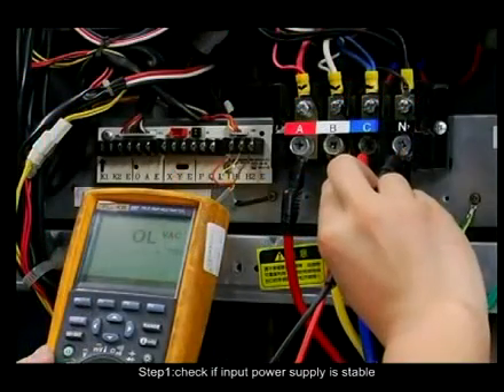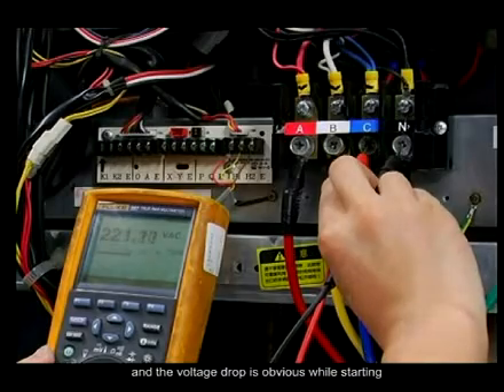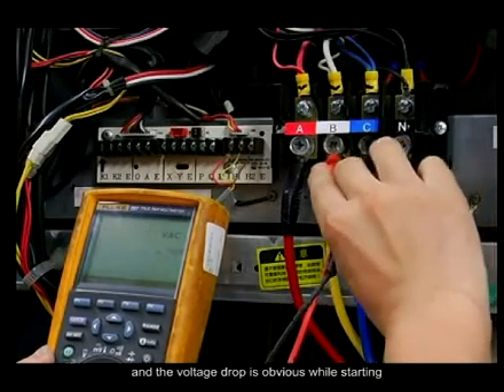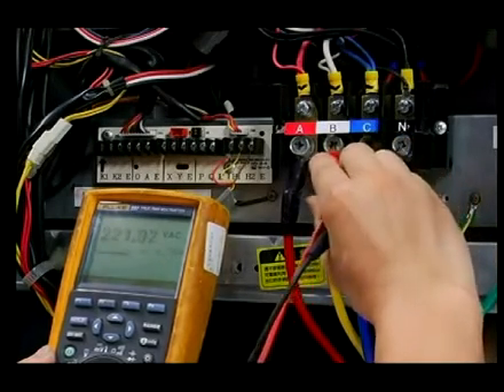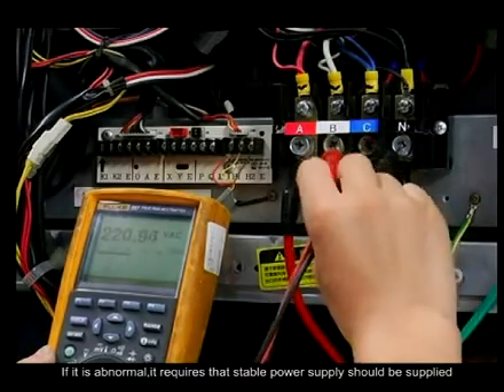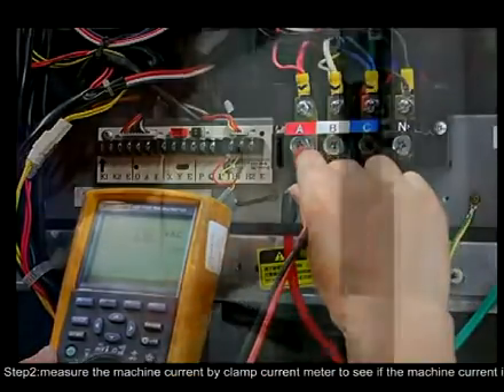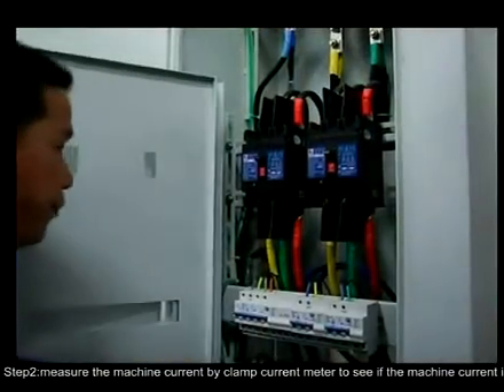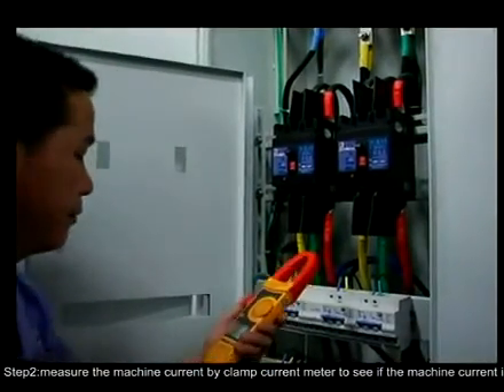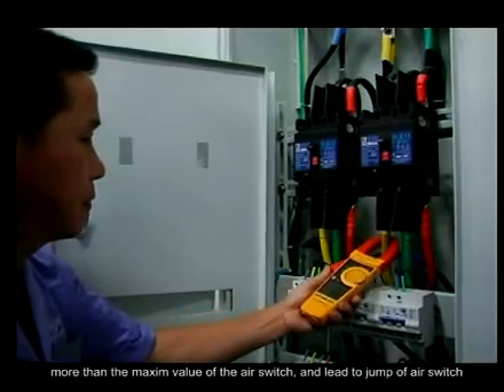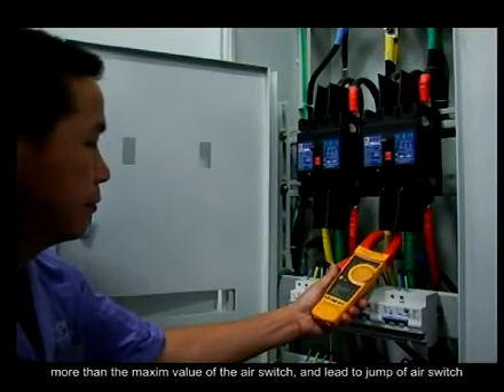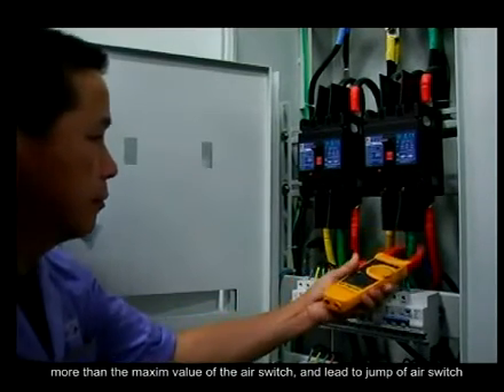Step 1. Check if the input power supply is stable and whether the voltage drop is obvious while starting. If it is abnormal, a stable power supply must be provided. Step 2. Measure the machine current with a clamp current meter to see if the machine current is more than the maximum value of the air switch, which would lead to the air switch jumping.